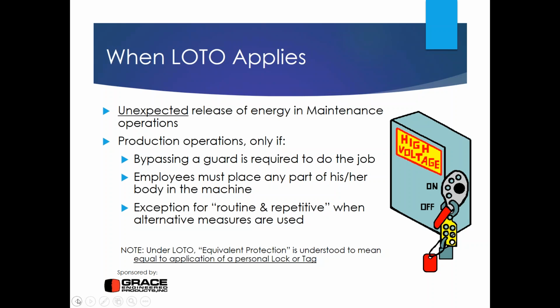So generally, all maintenance activities are assumed to be done on equipment that is in the locked out, tagged out state. When production operations are in play, it really applies primarily if you're going to do something like bypass a guard or remove a barrier from equipment such that it exposes either electrical hazards or some other hazard as well. And so in the production mode, primarily bypassing guards or putting any part of your body in harm's way would constitute the requirement to do a lockout, tagout. There is an exception for routine or repetitive work when alternative measures are used. I will cover what that would include in a slide or two, so we'll just park that one for the moment.